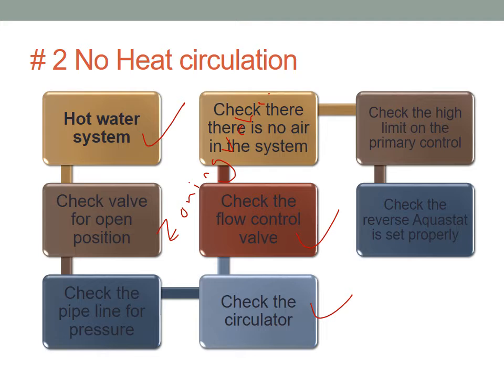What happens if there's air in the system? So the pump is running, water is pumping, but there's air. Water is not going to push air, go around air. Air is going to be compressed and the system is called air bound. So at this point you have to purge the system, same thing that you did with the oil pump.